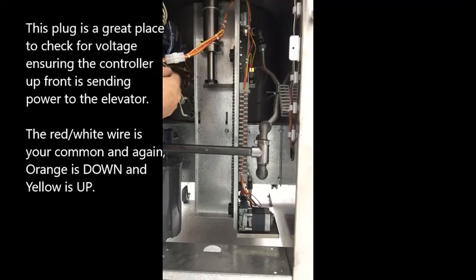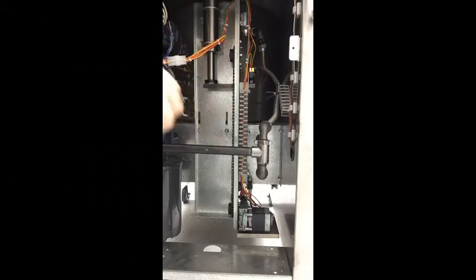So if you wanted to test for up, if you see the up command in the front, then you can go between yellow and red and check for 208, 240 volts. Or if you're going down, it would be the orange and the red. Same thing.